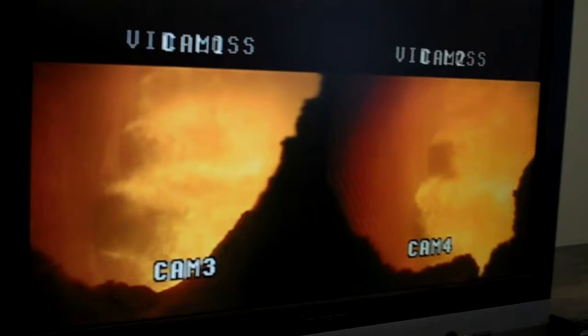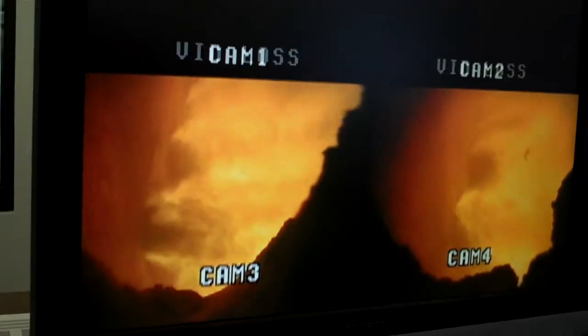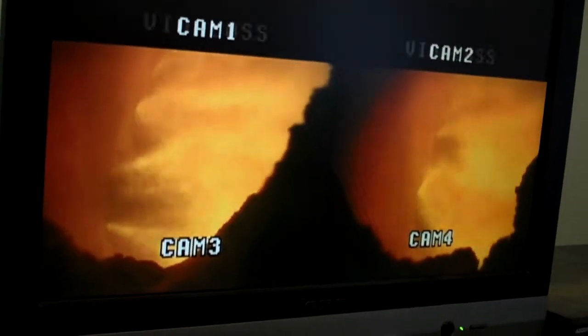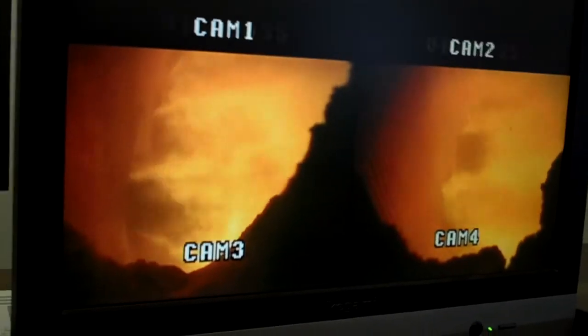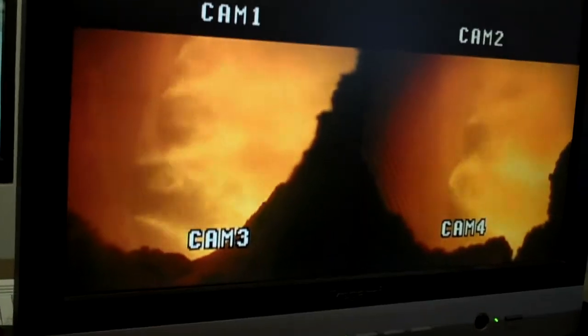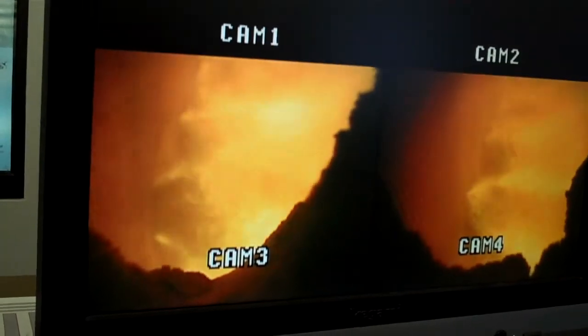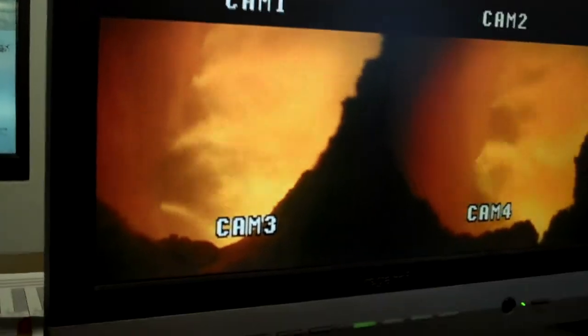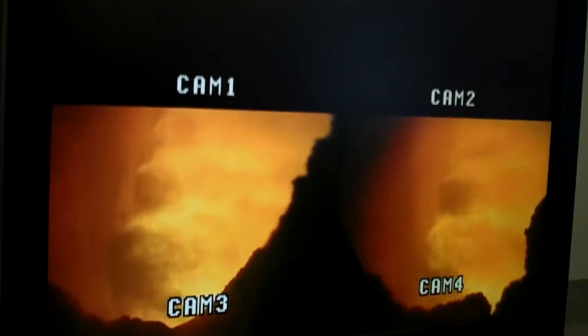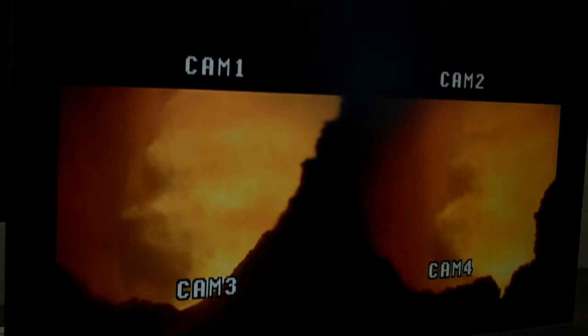How do you have a camera in there when it's so hot? It actually has purge air. The camera's in a port on the outside. You have purge air on the outside that's always blowing down the tube and keeping it cool. You can actually pull that tube out of there and put your hands in. Otherwise, no.